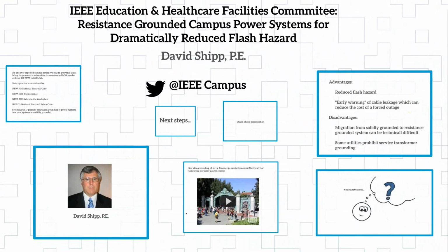Well, let me tell you one of the reasons, and what I'm going to do is take the high resistance grounding and or how they do it today for solid grounding at 480. And I'll do the 480 volt example because it's everywhere in the USA, but obviously if I could do it in a commercial building, I could certainly do it in a university. As long as it's above 150 volts, then you have the option. You don't have to solidly ground. But the main reason they were solidly grounding, if you go back 30, 40 years ago, is if I solidly grounded, it was cheapest. It was the safest if nobody knew anything at all, because any ground fault you get, it'd be big smoke and fire, trip something off, blow a fuse, and take itself out of service. But it was also the worst from service continuity.